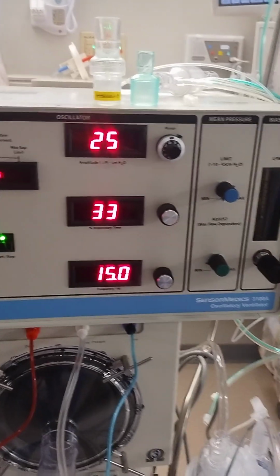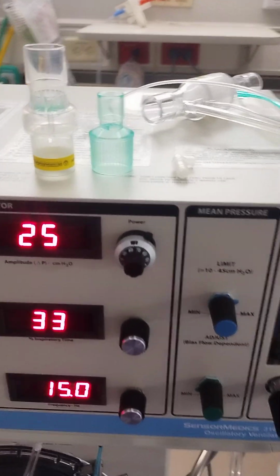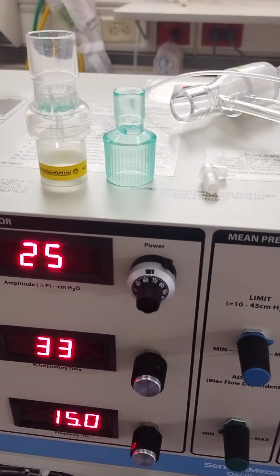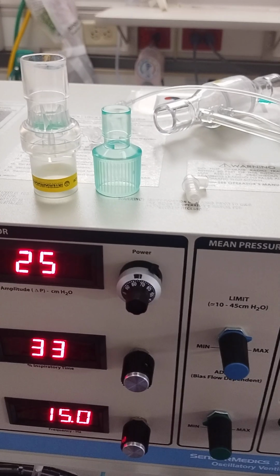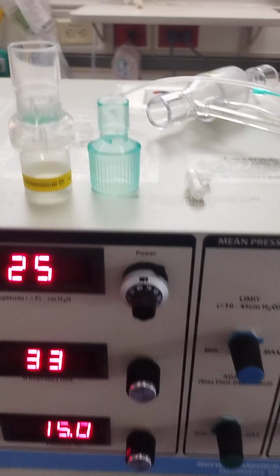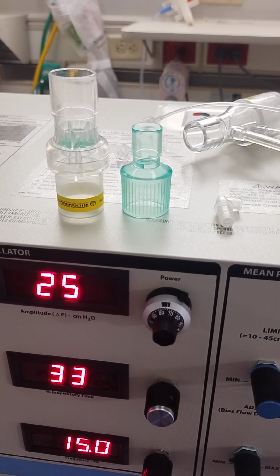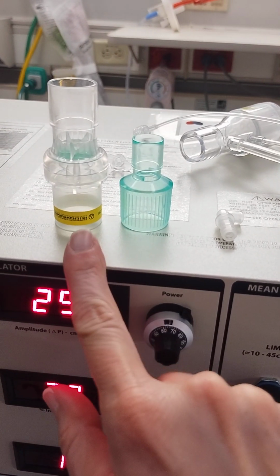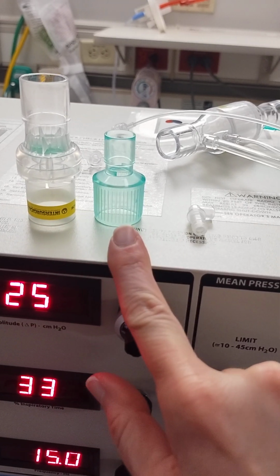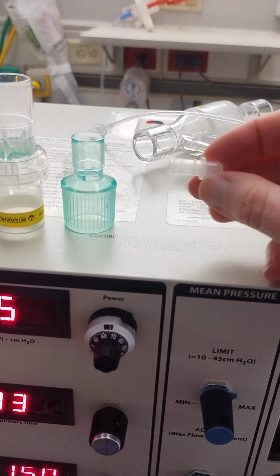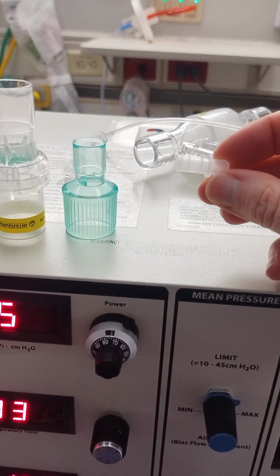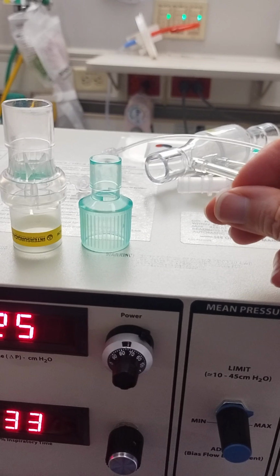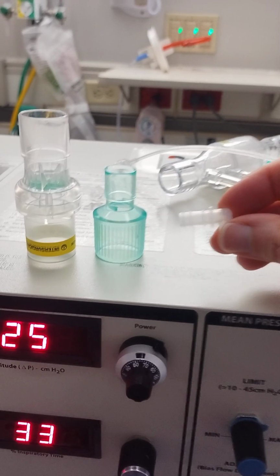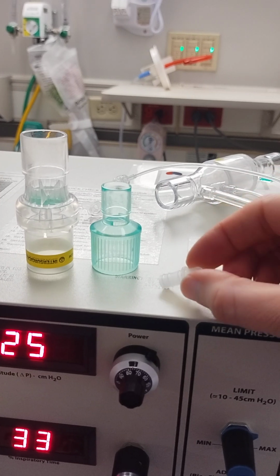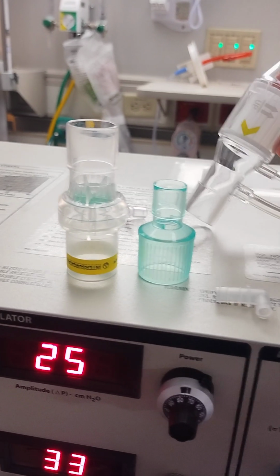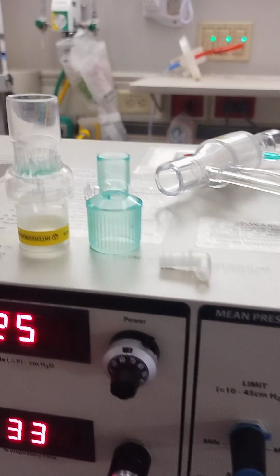So now we're going to go over how to attach the nitric oxide equipment in line with the oscillator. We have our various pieces here, and at our facility we use the NoxBox. For the oscillator we need the one-way valve, this adapter, and this little elbow. This elbow is actually in the 22 millimeter kit, so you'll have to get it from that kit because the 12 millimeter kit does not have this piece. And then we have our flow sensor here and also our sample line.